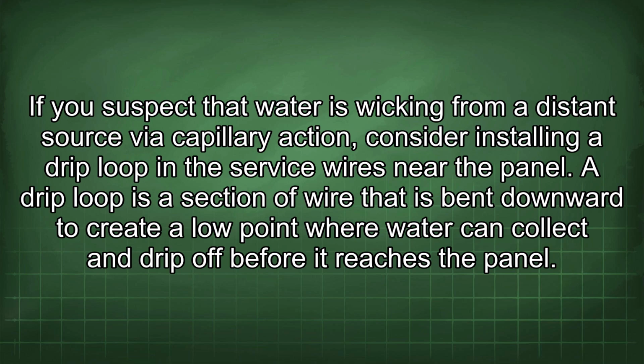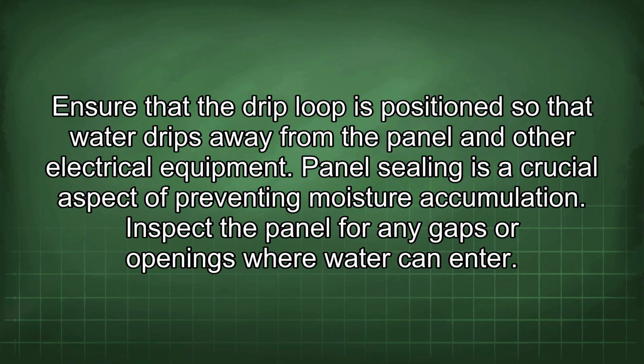If you suspect that water is wicking from a distant source via capillary action, consider installing a drip loop in the service wires near the panel. A drip loop is a section of wire that is bent downward to create a low point where water can collect and drip off before it reaches the panel. Ensure that the drip loop is positioned so that water drips away from the panel and other electrical equipment.